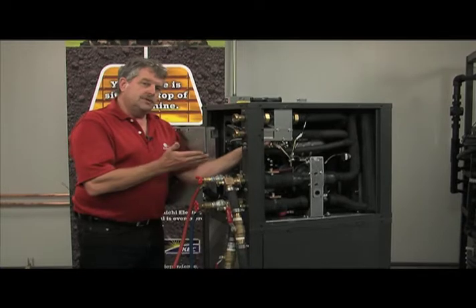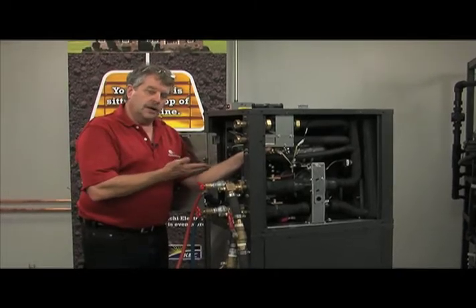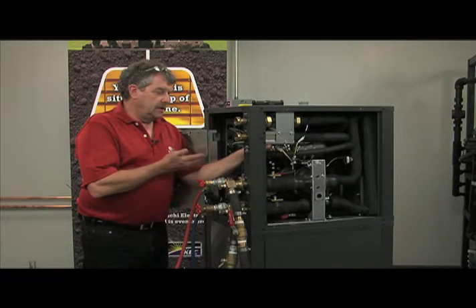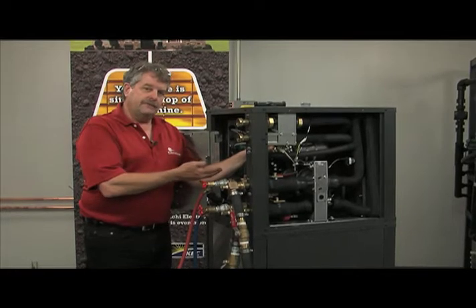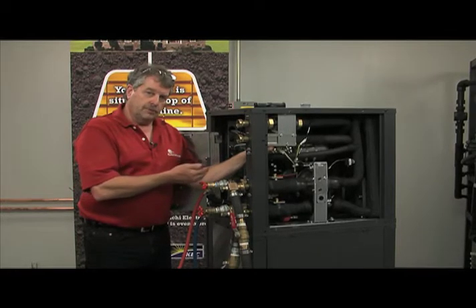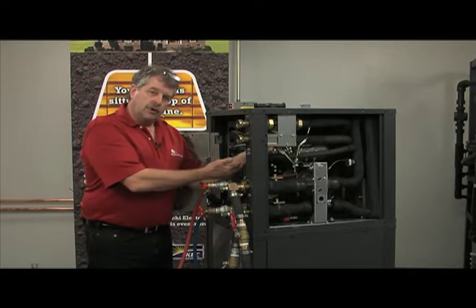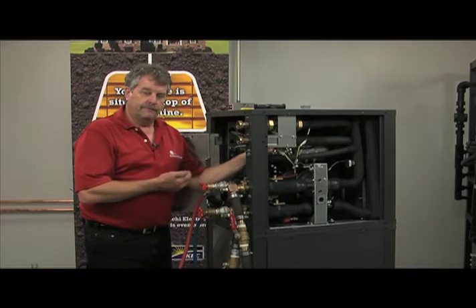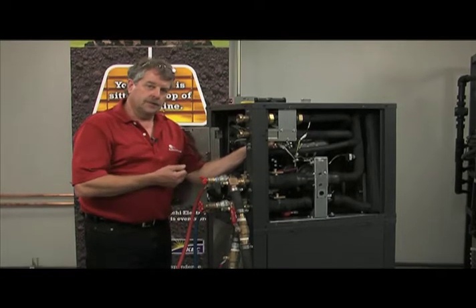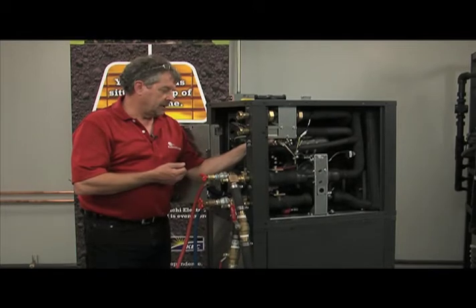Because there might be a situation where you'll have to remove the expansion tank, I'm going to leave that valve open, so when I bleed the pressure off the unit, I'm also discharging that fluid volume we've got up against that bladder in the expansion tank.